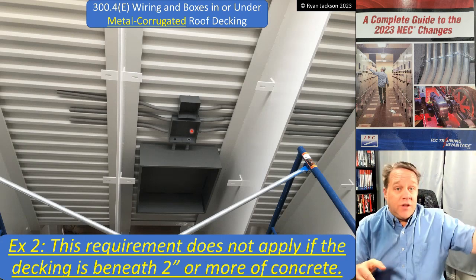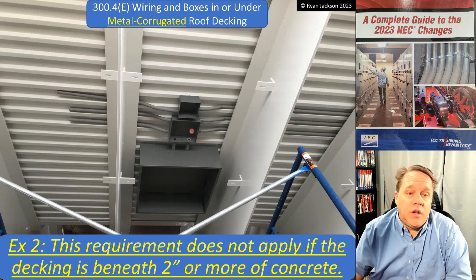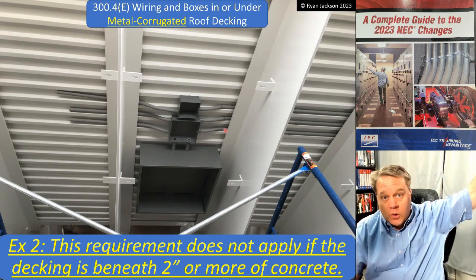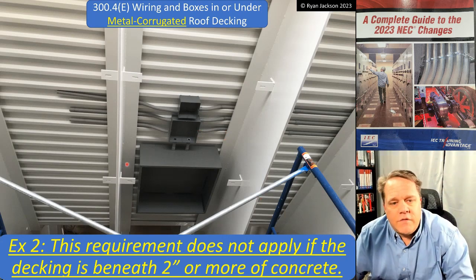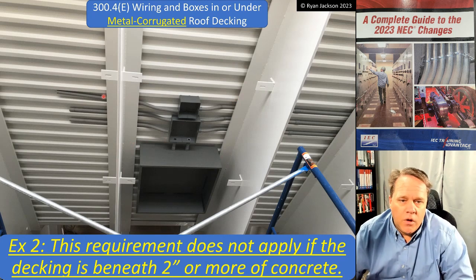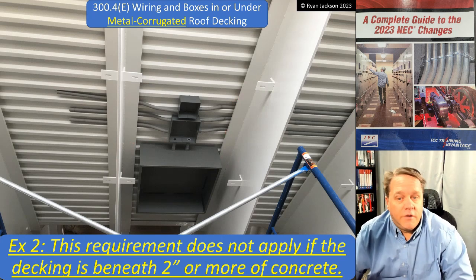So if you've got a 10-story building, you probably only need to worry about this requirement for the 10th floor, not floors 1 through 9. So do we have a violation in this photograph? No, not if there's 2 inches of concrete above it. So nice clarification.